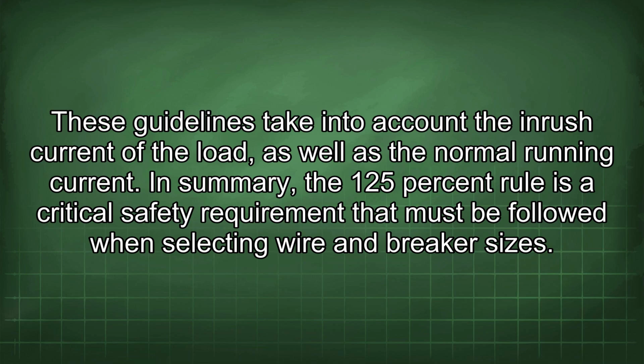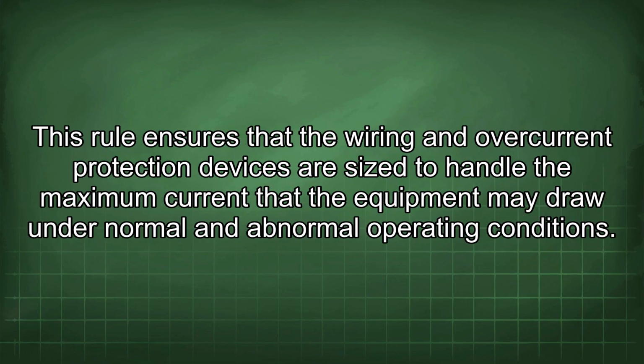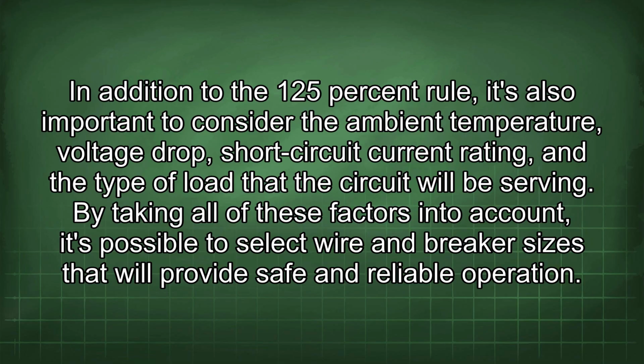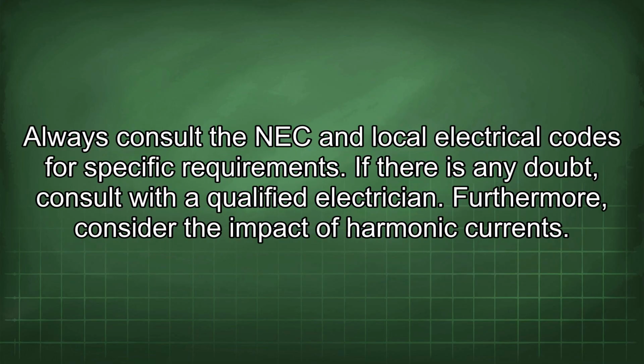In summary, the 125% rule is a critical safety requirement that must be followed when selecting wire and breaker sizes. This rule ensures that the wiring and overcurrent protection devices are sized to handle the maximum current that the equipment may draw under normal and abnormal operating conditions. In addition to the 125% rule, it's also important to consider the ambient temperature, voltage drop, short circuit current rating, and the type of load that the circuit will be serving. By taking all of these factors into account, it's possible to select wire and breaker sizes that will provide safe and reliable operation. Always consult the NEC and local electrical codes for specific requirements. If there is any doubt, consult with a qualified electrician.